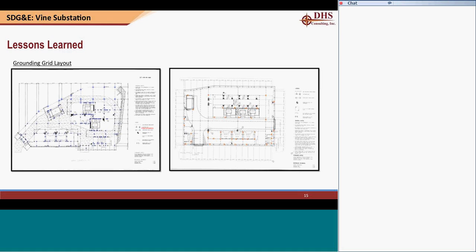They bid off of the Mira Sorrento grounding grid plan. So what I did was take that plan, put it in Bluebeam, and did a quick takeoff. We figured out how many exothermic connections, how many ground rods, how much 4-aught wiring, how much 500 kcmil, and I came up with totals to compare with the new design we had just received.